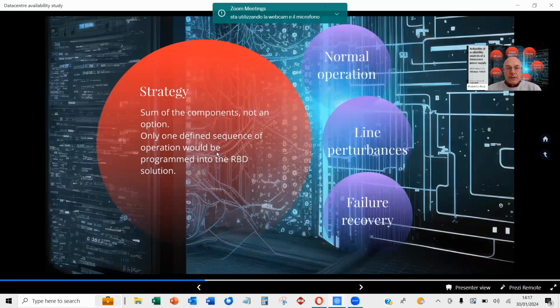Strategy-wise, the sum of components typical of, say, a reliability prediction was not an option. Only one defined sequence of operation would be programmed into the RBD solution, but we had to be flexible to design recovery that impacted a single unit, a single system - those A to L systems - or the whole data center.